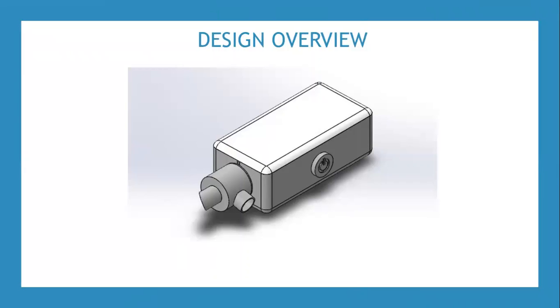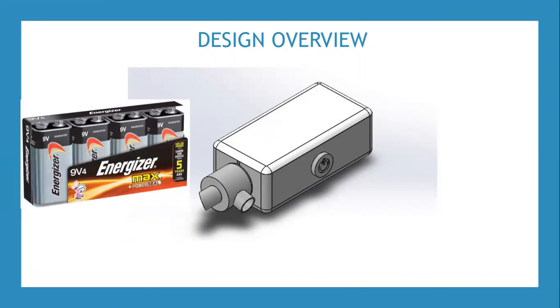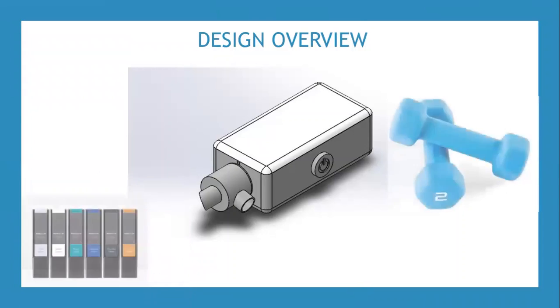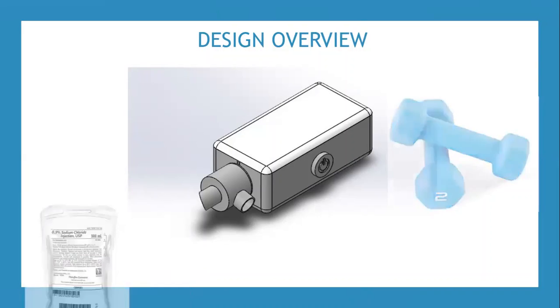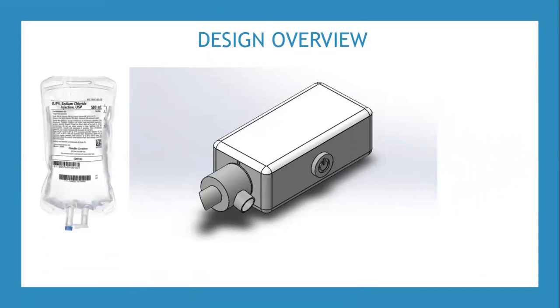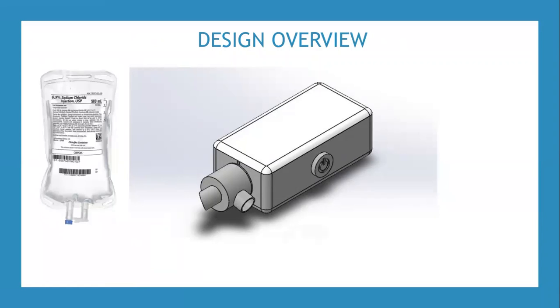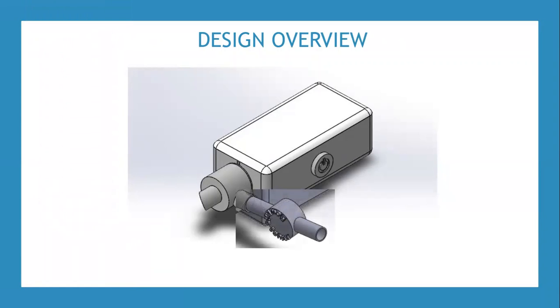To satisfy the functional requirements, we chose to power the device with a 9-volt battery so it can be portable and reusable as long as the battery maintains full strength. We made sure the device weighed below 2 pounds by choosing a light, durable, and affordable plastic material for all the custom components, satisfying 3 customer requirements at once. This allowed the device to administer a standard 500 milliliter saline bag in 2 minutes. Lastly, we incorporated a flow rate sensor to monitor and act as feedback for the user, satisfying the majority of our customer requirements.